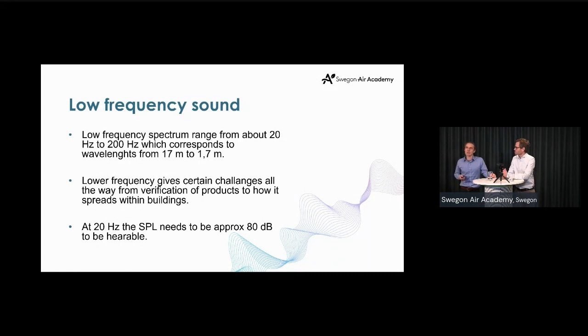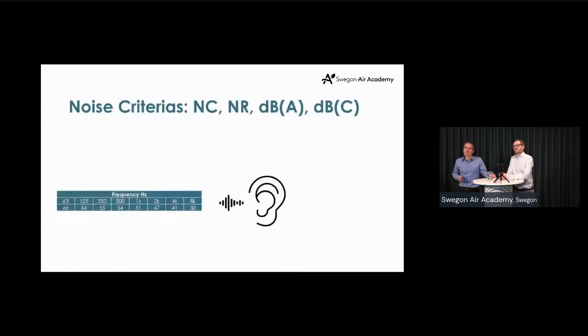Before we speak about challenges, just a few words also about noise criteria. Because somewhere in the end, we need a criteria to understand the level of the sound and how it affects us, or to have something to verify and measure against, like a European standard, ISO, ASHRAE, or a national standard. Depending on where in the world you are, you might encounter NC, NR, dBA, or dBc. By a short example, if we look here at 8 octave bands, ranging from 63 hertz up to 8 kilohertz, which is standard in the HVAC industry.